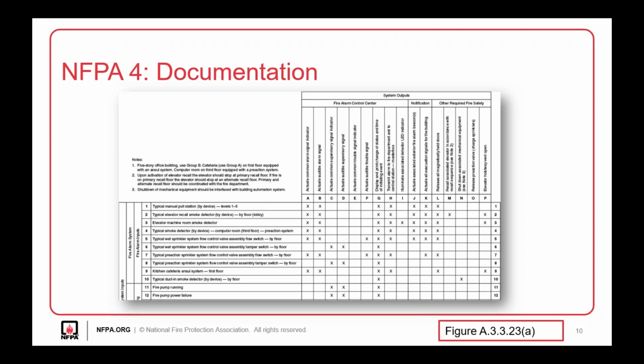power. And then during the testing, it's likely that things will not perform as expected, and there are going to be some issues that arise. Because of that, it's important to maintain a proper issues log and a corrective action report. The issues log outlines every time there's an issue with the tests. So let's say you were testing a smoke control system, but a few of the doors in that smoke control zone barrier didn't close. That would be put in the issues log, and then it needs to be assigned to someone to fix. Then once that issue is fixed, the person who performed the repair would then complete a corrective action report.